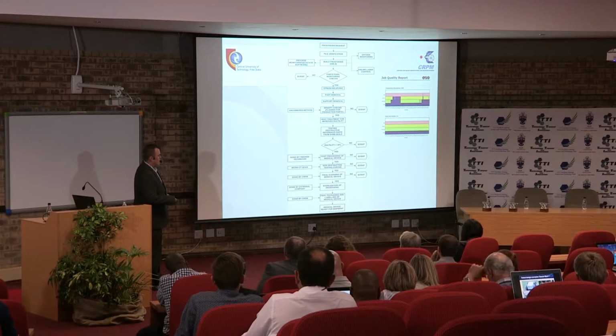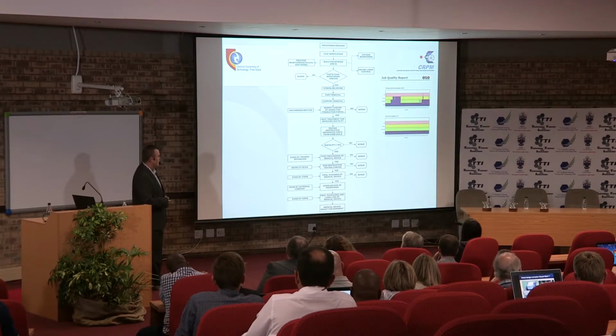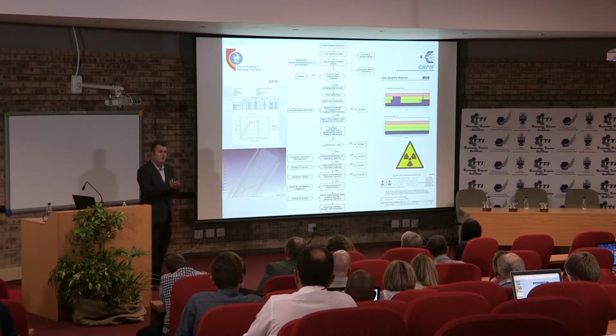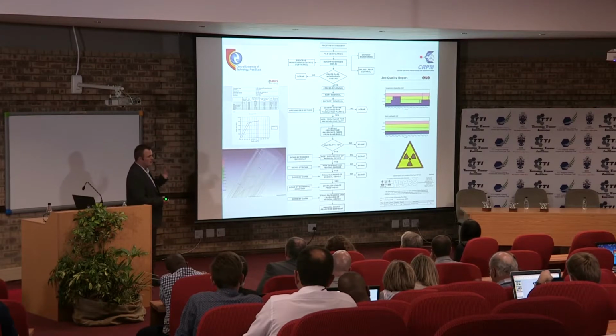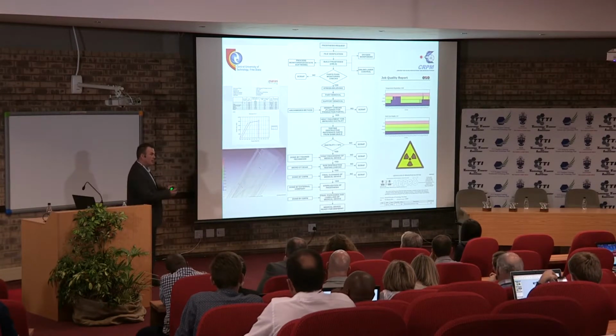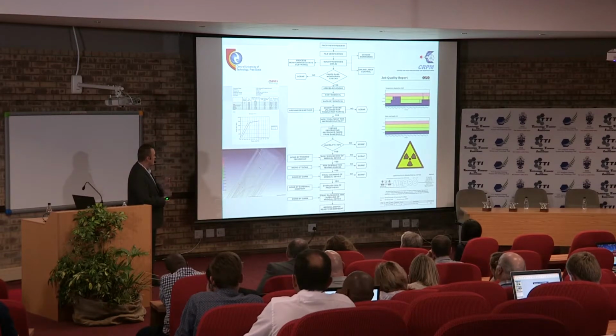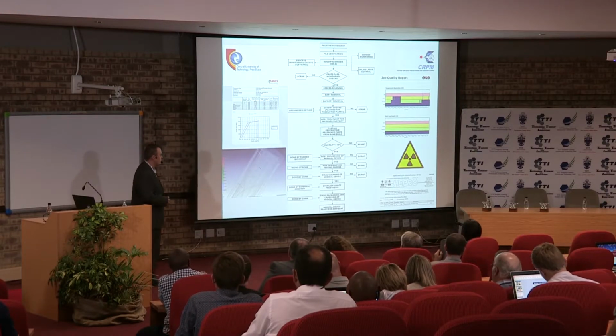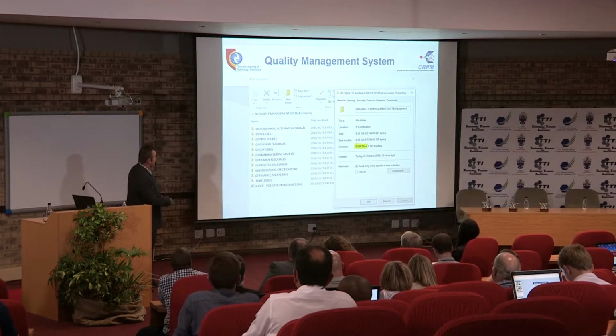That's plus minus 8 to 10%. So a lot of post-processing is polishing and non-destructive testing. That's done at Stellenbosch University with their micro and nano CT scanner. Then final cleaning and sterilization of the prosthesis is also done outside at EPRO at this stage. This is the non-destructive testing that we're currently doing also to create the history. If we're now doing 100 implants, we can see what the trend is. With this ISO system we also need to plot statistics, accuracy, and the strength of the implants over time. And you can see here just a tensile test. Then from there it's labeled and goes off to the hospital.